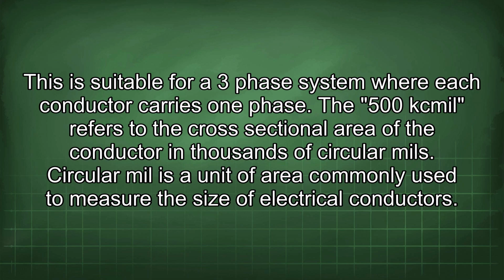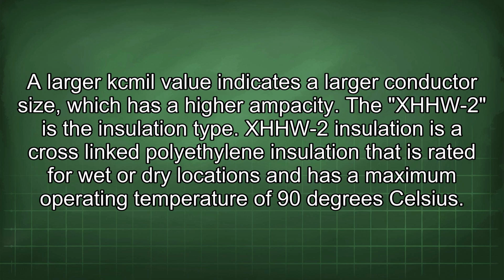The 500 kcmil refers to the cross-sectional area of the conductor in thousands of circular mils. Circular mil is a unit of area commonly used to measure the size of electrical conductors. A larger kcmil value indicates a larger conductor size, which has a higher ampacity. The XHHW-2 is the insulation type. XHHW-2 insulation is a cross-linked polyethylene insulation that is rated for wet or dry locations and has a maximum operating temperature of 90 degrees Celsius.